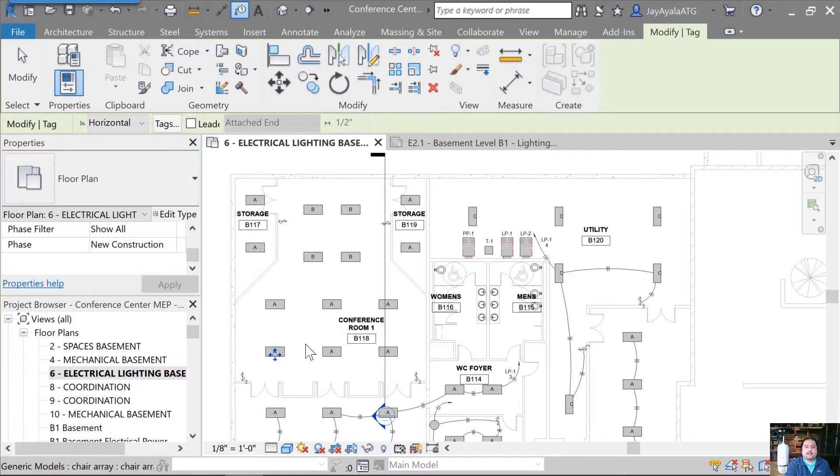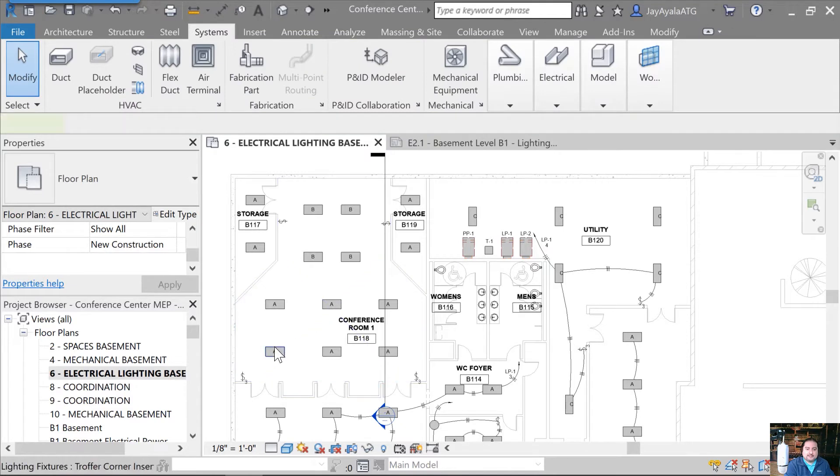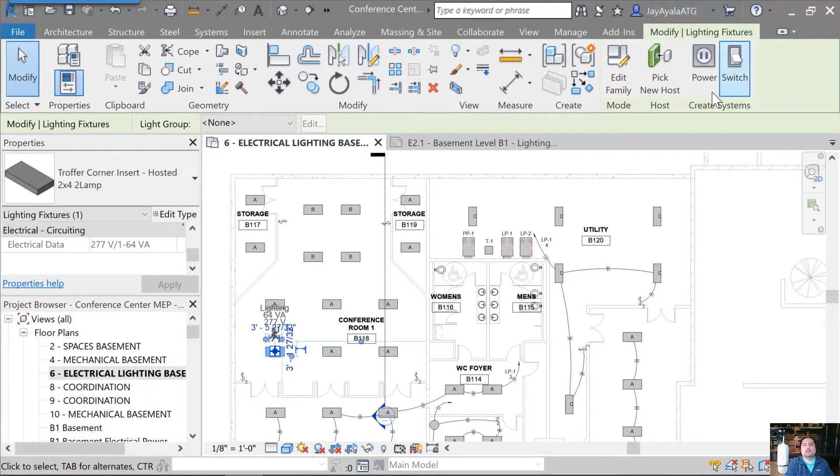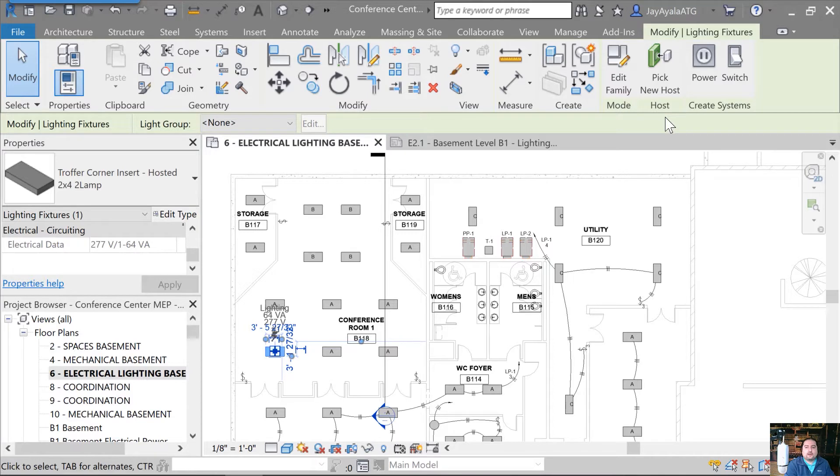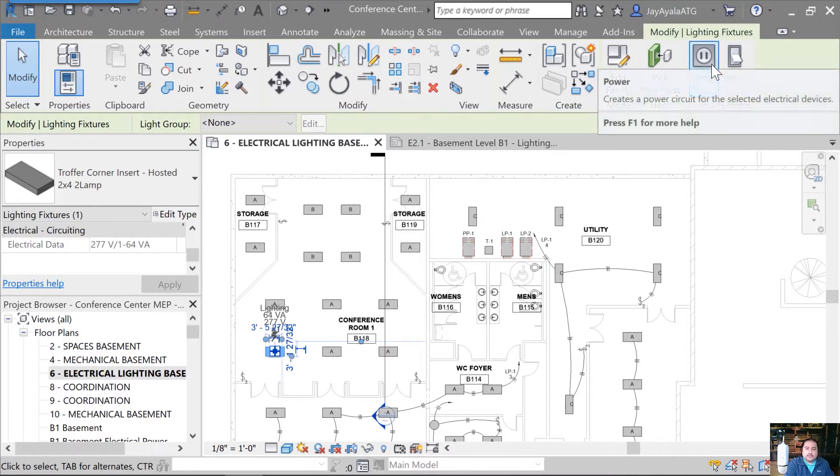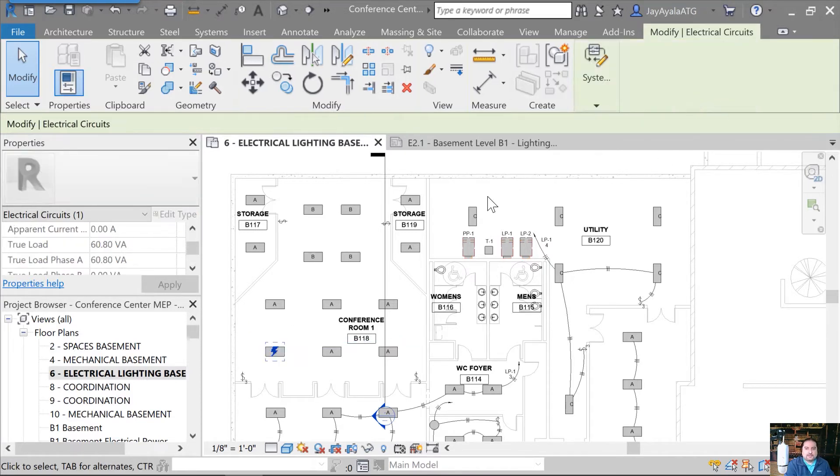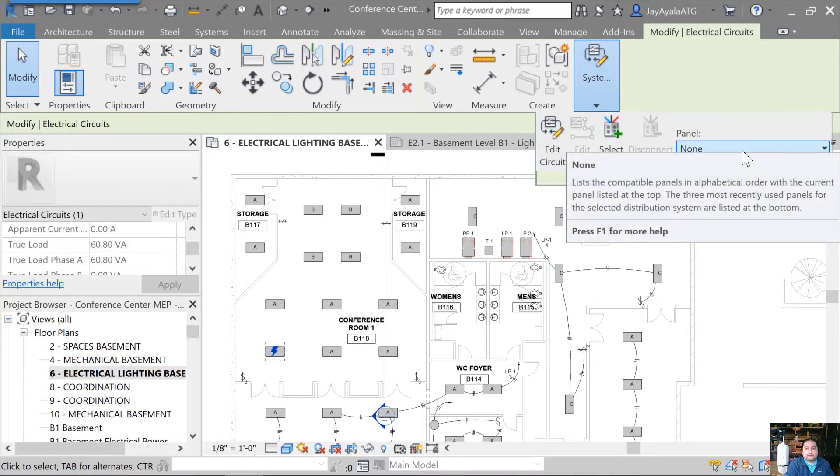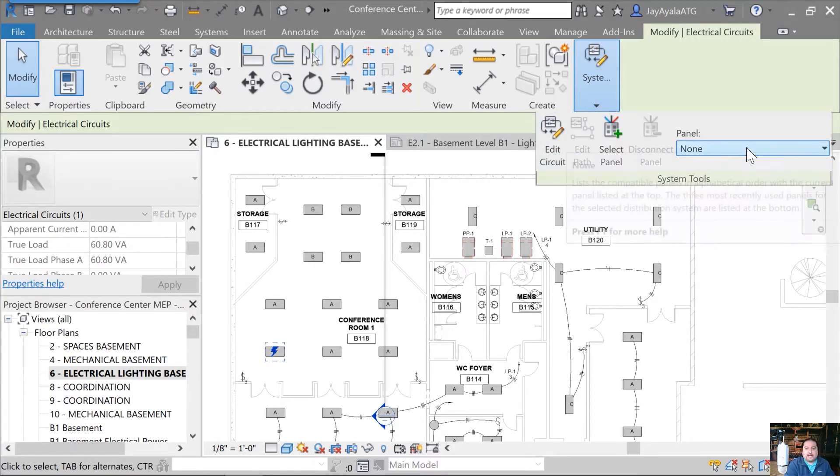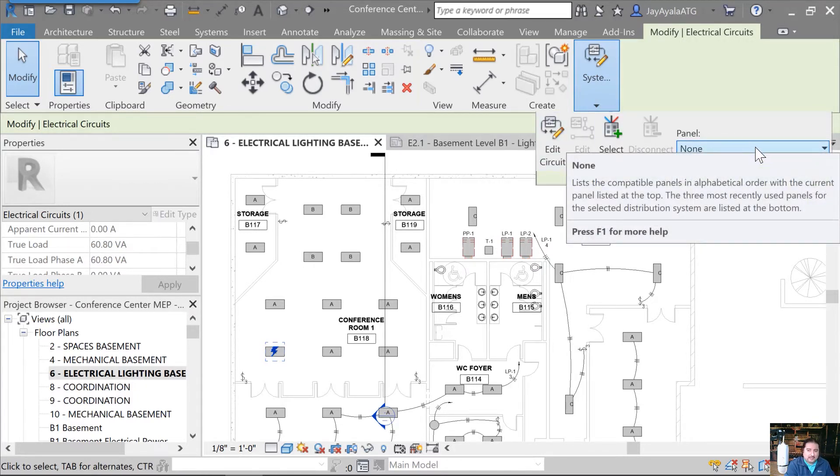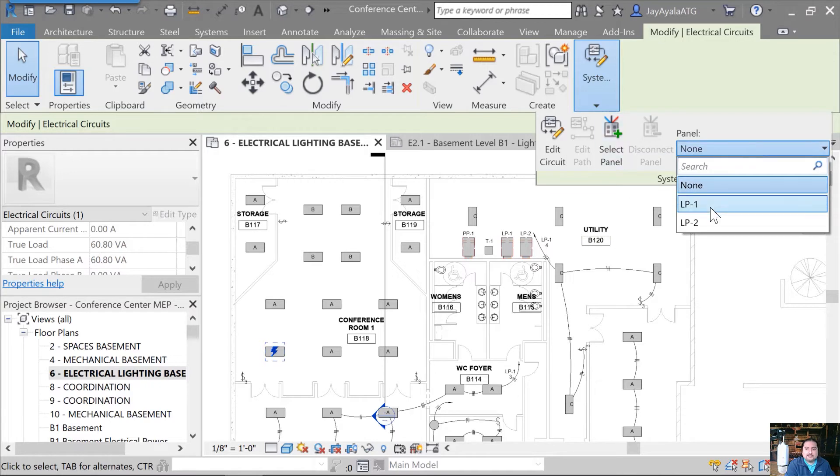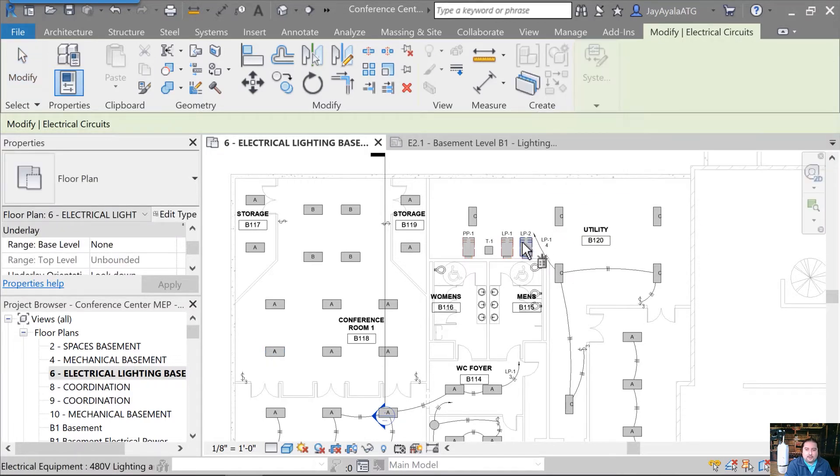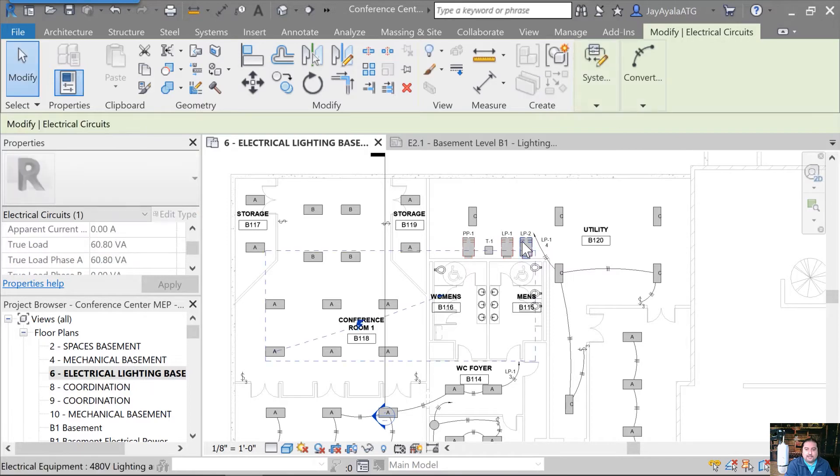I'll start by selecting that light. That's it. Select the light. Once that light is selected, you're going to see in the modify lighting fixtures contextual ribbon, the one that's colored green over here, we can see that we can create a system and here's a power system. So once we create this power system, we've got this other contextual ribbon that helps us edit the circuit and also select the panel from the list, or I can simply choose LP-2 here, or I can simply go click on the panel that I want to add.